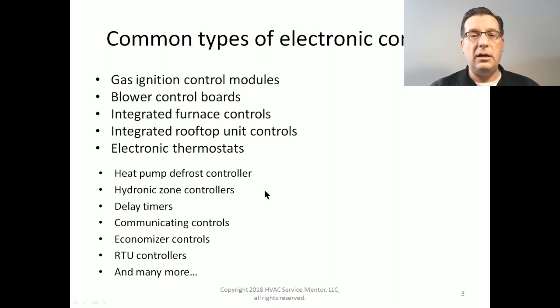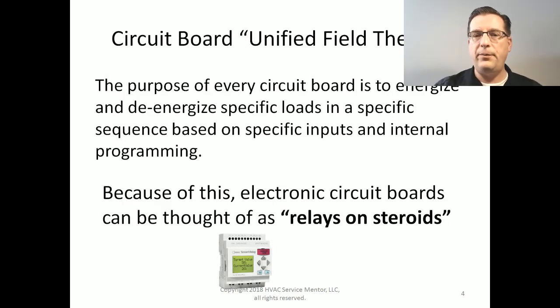Some other types of controllers we'll find are heat pump defrost controllers, hydronic zone controllers if you do any boiler work, delay timers. They're very, very common in condensing units. Communicating controls, a whole different animal. We'll talk a little bit about communicating controls. Economizer controls on light commercial package rooftop units, and lots of other things. They are literally everywhere. They're in your toaster, or at least your toaster oven.